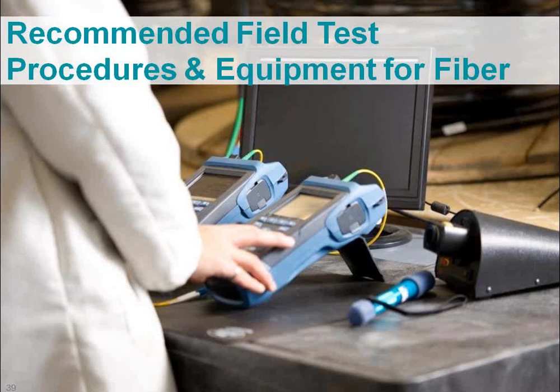Launch and receive cables that are poorly handled. Many people think that when they pay top dollar for a launch cable or receive cable, it should never fail, when that's false. If not handled properly, after a number of matings and testing connectors, the connectors will wear, chip, and break. It's the same glass as the cable under test. These do have to be repaired, either cut off, new connectors added, or repolished. The cable itself will last a long time, but the connectors will always need to be repaired. And Alliance has repaired and replaced many of these over the years.